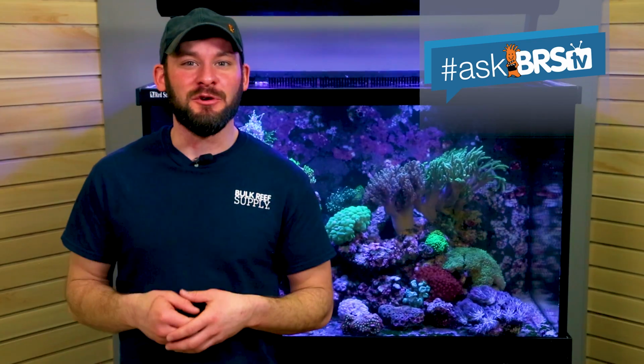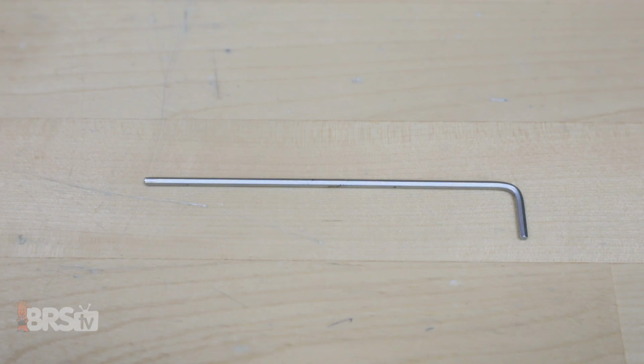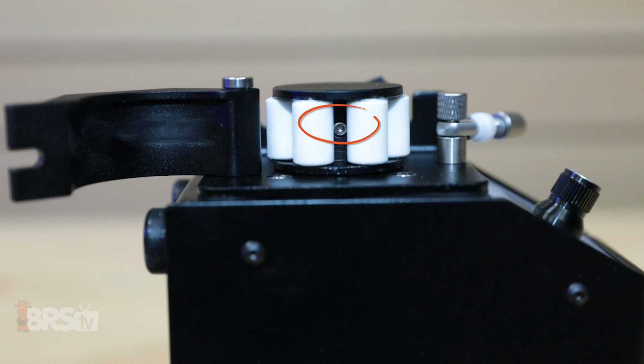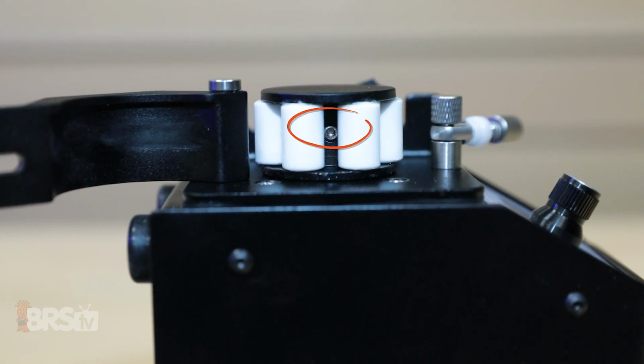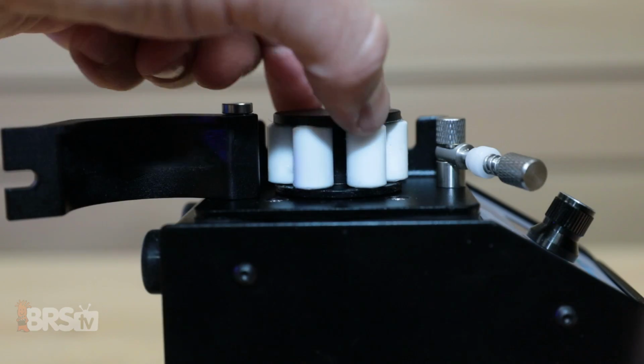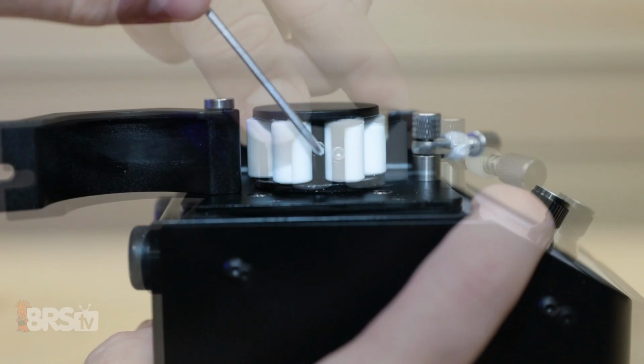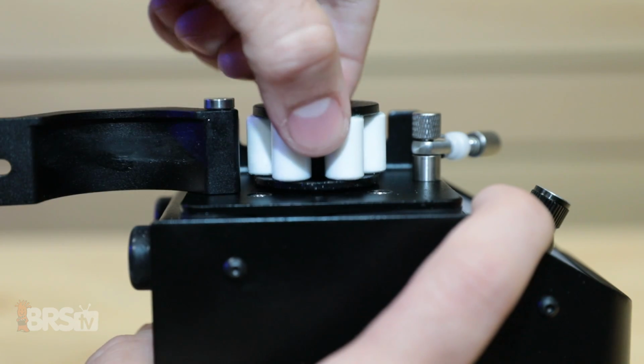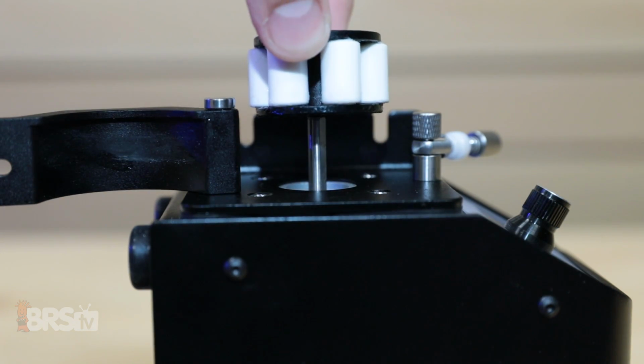For the dosing head removal and replacement, you'll need a metric size 2 Allen wrench to loosen the retaining screw that holds the pump head onto the motor shaft. Just spin the head until you see the screw in between the rollers, loosen it enough to pull the head off the shaft, and then put the replacement back on in its place.